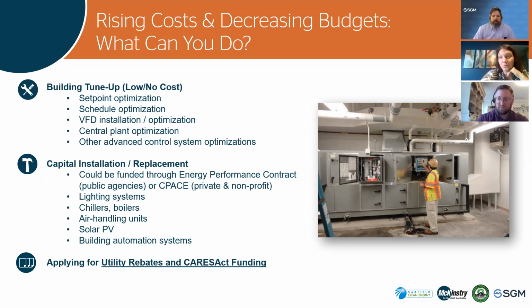There was a question from someone about the added filters and UV: does that make it safer to use return air? And I want to address that just saying, yes, it does make it safer to use return air and not have to use as much outside air, but it can still give you a false sense of security. Your maintenance on these systems needs to be almost doubled, checking those filters, making sure coils are clean, and making sure UV systems are working.